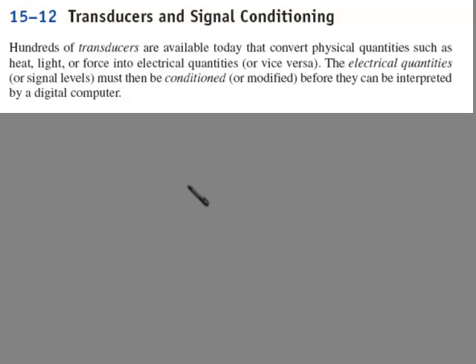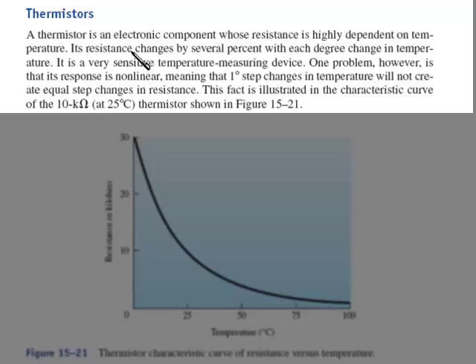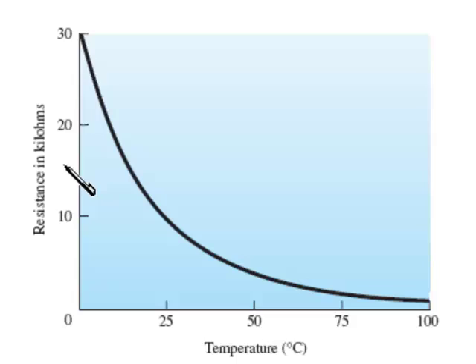So the first sensor we'll look at is the thermistor. This is an electronic component whose resistance is highly dependent on temperature. Its resistance changes by several percent with each degree change in temperature. It's a very sensitive temperature sensing device. One problem, however, is that its response is non-linear, meaning that one degree step changes in temperature will not create equal step changes in resistance. This fact is illustrated in the characteristic curve of the 10K ohm at 25 degrees C thermistor shown below. And you can see that as the temperature increases, the resistance drops, but it's not a straight line. It's a non-linear function.